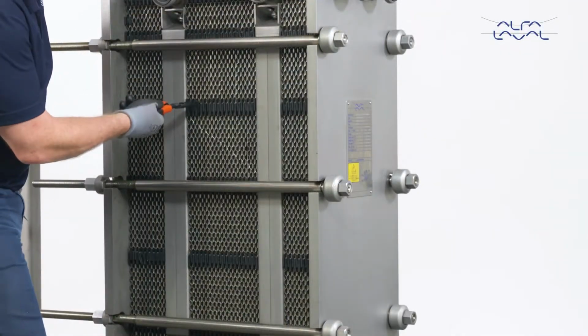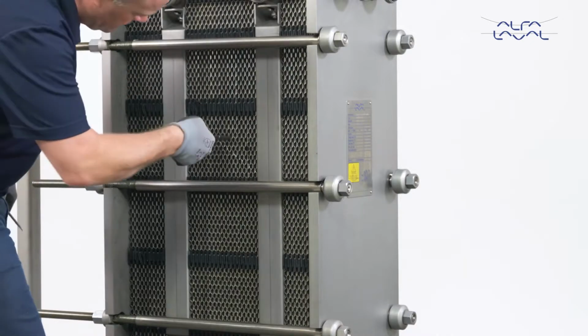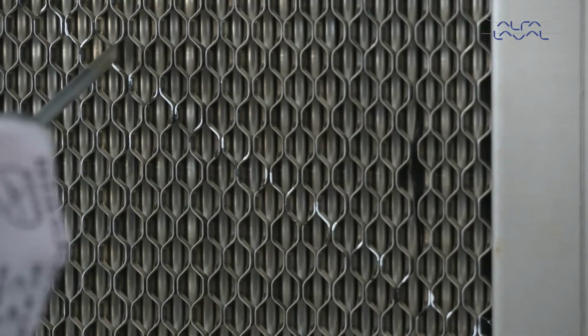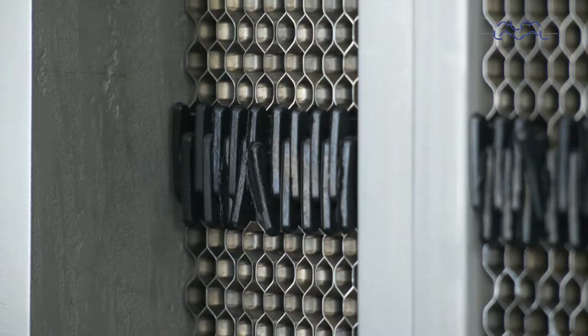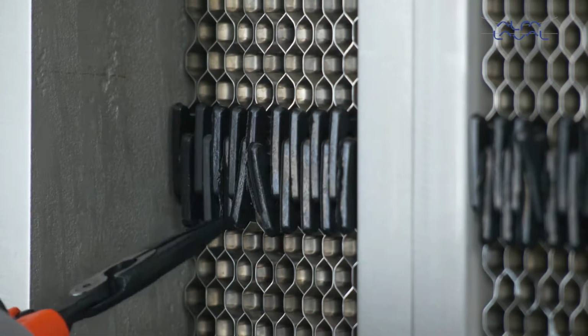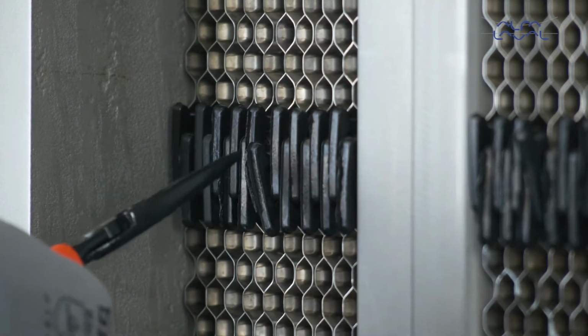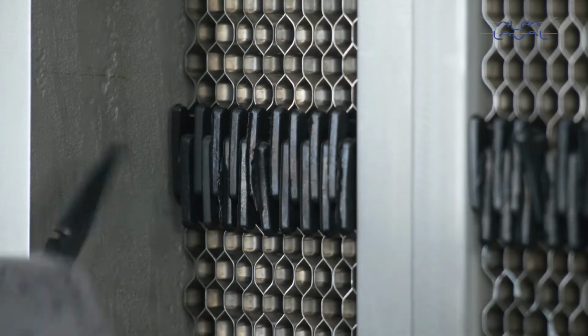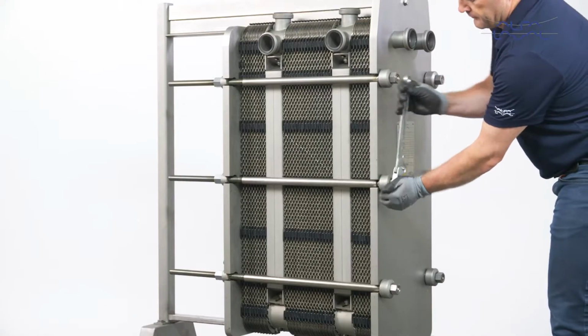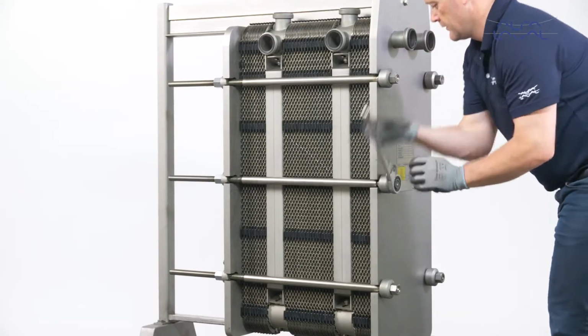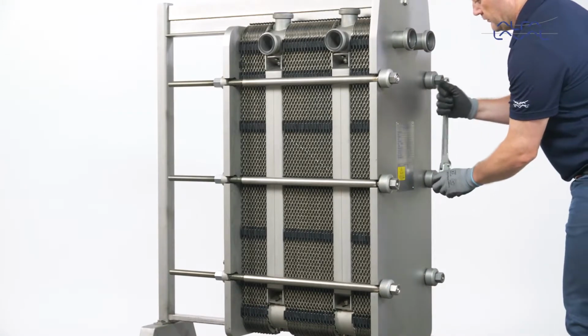While tightening the bolts, check that all gaskets are securely fitted in the gasket groove. If any gaskets are protruding, press them firmly back into the gasket groove using a pointy but blunt instrument. Be sure to also check that all gasket clips are positioned correctly and securely in place. While tightening the 4 tightening bolts, be sure to also tighten the locking bolts.